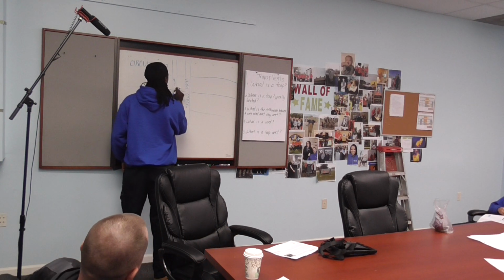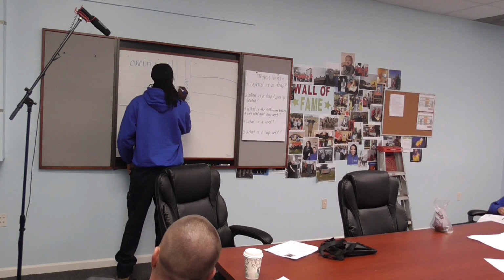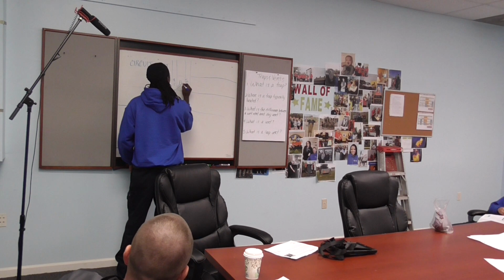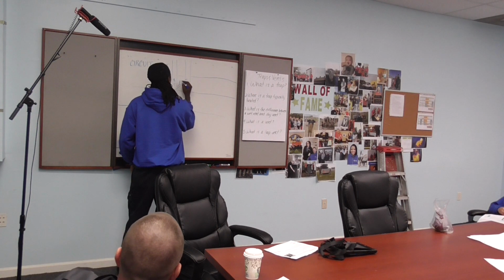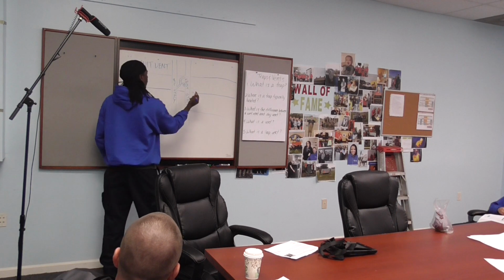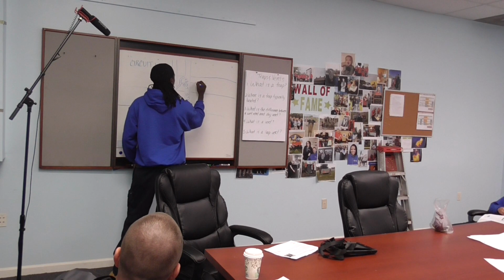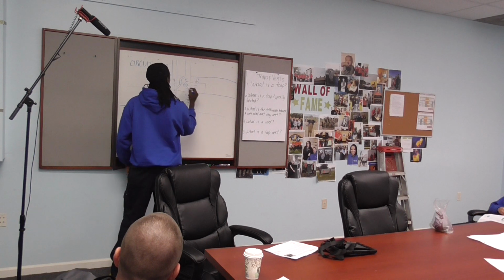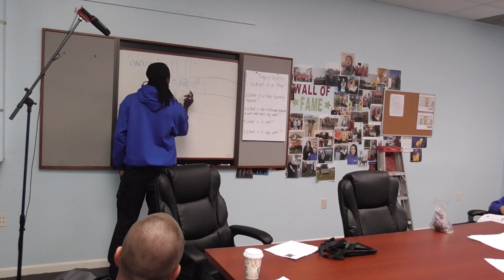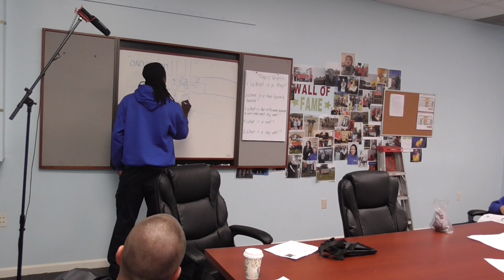So basically, I cut a Y in, and then right in the middle, I put a T in. And then I put my trap. Then right at the top of that T, I tied it right back into the vent. So in the middle here, this is your sink or whatever, your kitchen sink. This will tie right into that. So now you have your venting and you have your soil. And you did that on every floor. We did it on every single floor, and that's what you call a circuit vent.